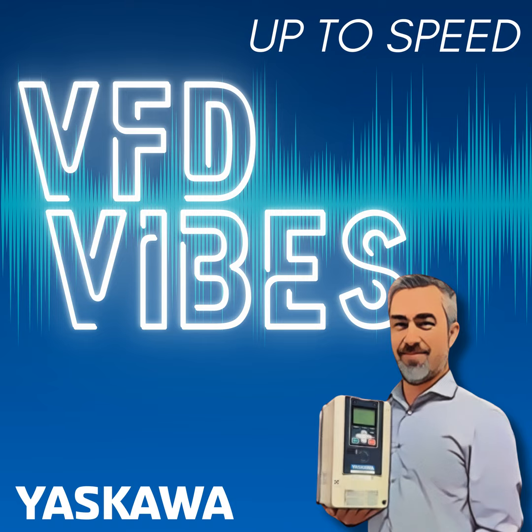So if you were starting 3 or 4 large motors across the line, even though it's only a couple of seconds of very high usage, that will actually drive up your rate for the entire month on the demand side. And another smart thing to do, if you're a facility with really large motors, is to have them on delayed or timed startups, or somehow sequence them so they can't start up at the same time. And you will save yourself money on that peak demand portion of your utility bill.